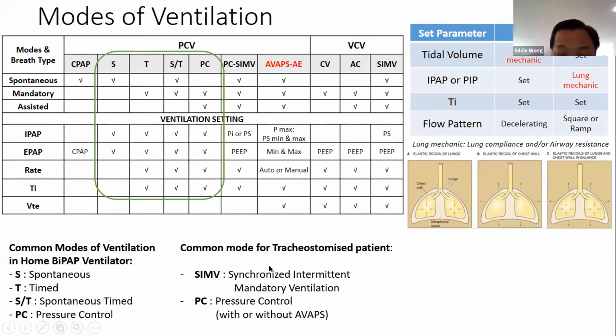So if the patient has a tracheostomy, if you have a tracheostomy tube put in your neck, the doctor normally will use either one of these modes, SIMV mode or pressure control mode. SIMV stands for synchronized intermittent mandatory ventilation. PC stands for pressure control, with or without AVAPS. AVAPS is a special mode from Philips. It stands for average volume assured pressure support. The doctor will set a target volume, so the machine will automatically adjust the pressure in case there are changes in lung mechanics.